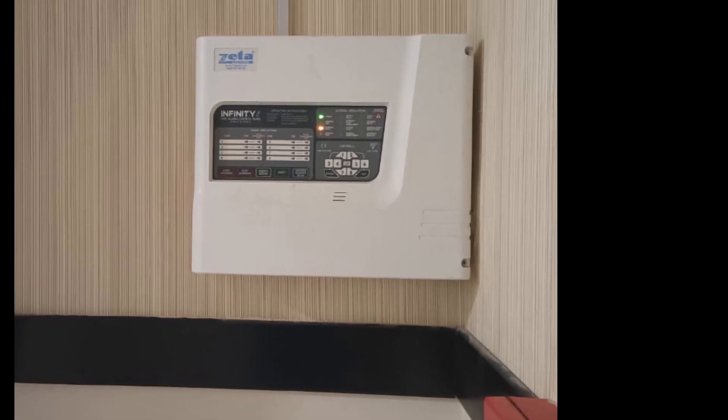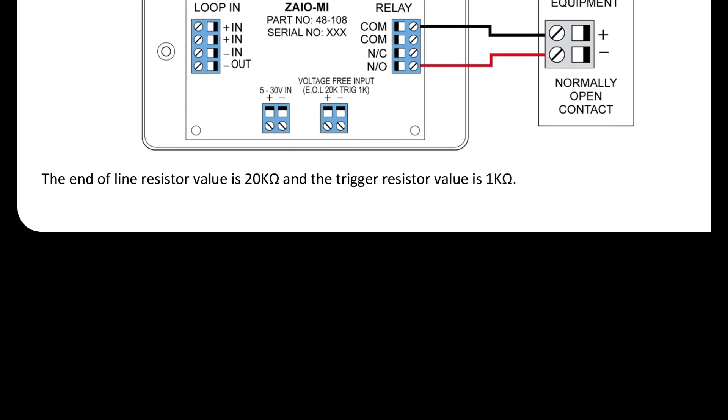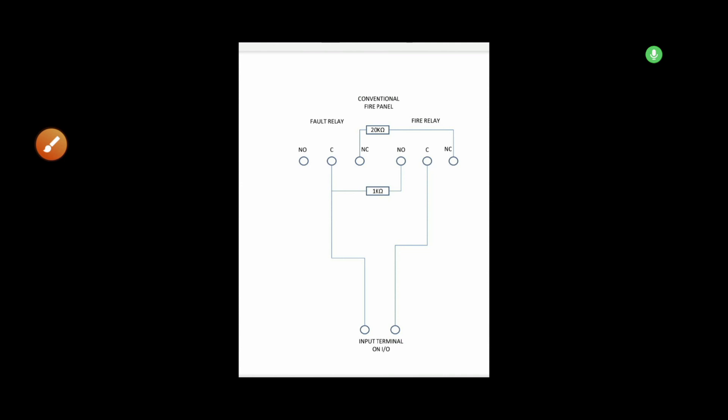In this video I will show you how to interface an addressable panel to a conventional panel. This is the schematic diagram of the interface between an addressable panel and a conventional panel with triggering alarm. If any alarm comes in the conventional panel, we also need it in the addressable panel — our main control panel.